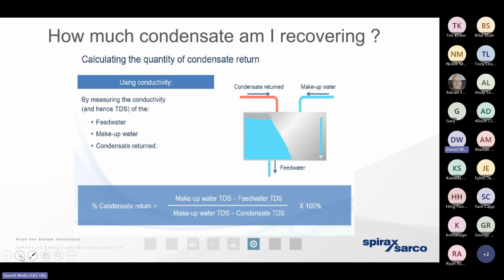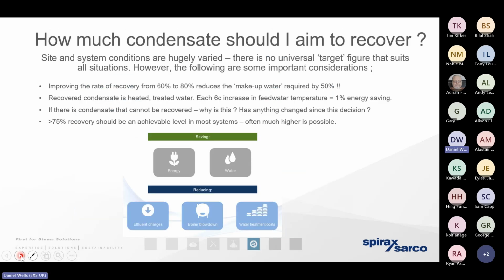So the question our client typically asks us is, well, how much condensate am I recovering? We don't know because we don't know what our client is using the steam for. They could be using it for indirect processes or direct processes. But by using the formula on the bottom of the screen, by taking the conductivity of the water in different areas of the boiler house, we can get an understanding for how much condensate is being recovered. Simply put, condensate is already chemically conditioned. It's in a fantastic condition for going back into the boiler. So a chemical understanding of condensate return is every bit as good as mechanical or metered recovery. So a client would then typically ask us, well, how much condensate should I be recovering?